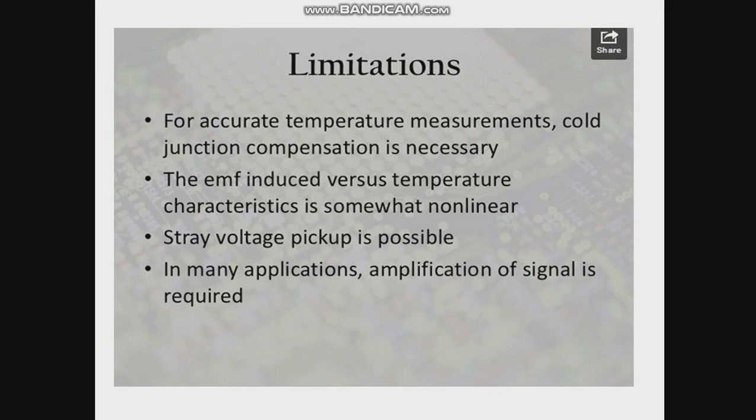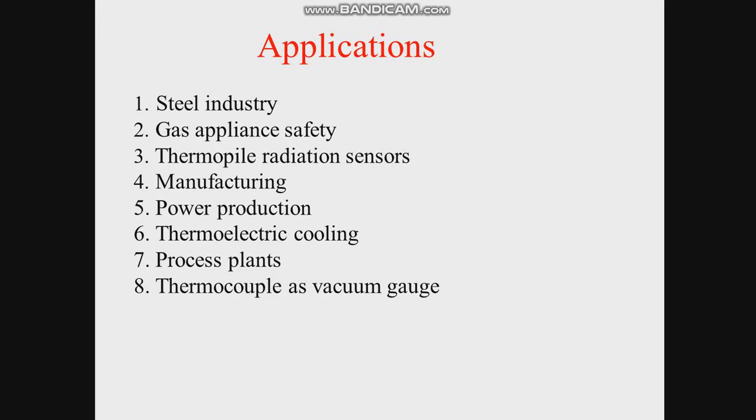Drawbacks: for accurate temperature measurement, cold junction compensation is necessary. The EMF induced versus temperature characteristic is somewhat non-linear. Stray voltage pickup is possible. In many applications, amplification of the signal is required.